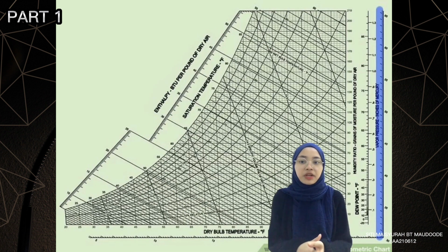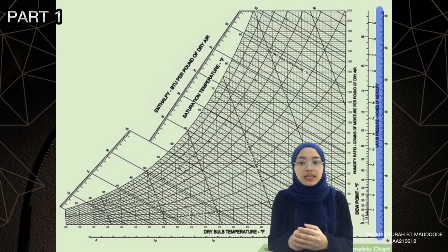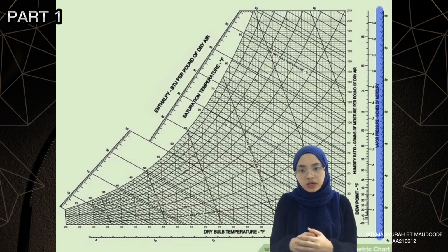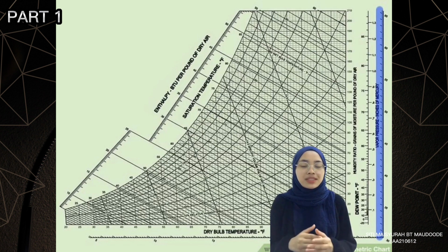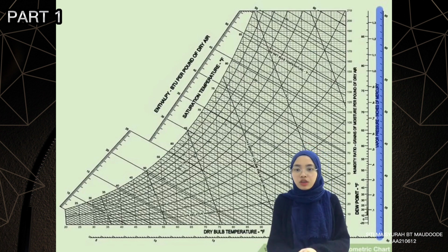Secondly, locate the vapor pressure line to the right of the dew point line, next to or along the same vertical line as the dew point measurement. There will be markings denoting the various vapor pressures in inches of mercury or millibars. Again, if you are having trouble following the line on the chart, use a ruler horizontally to align the hash marks on the vapor pressure with the line on the chart. Like dew point, vapor pressure remains constant even if the dry bulb temperature changes.